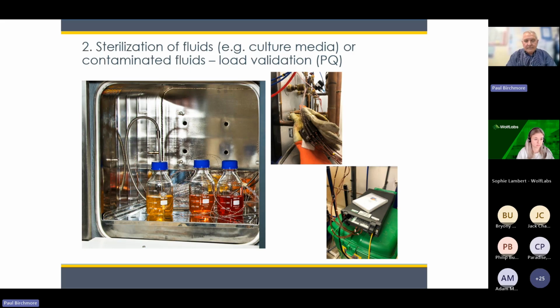That's the sort of default setting. But you can test. You can then go a step further and prove evidence of that effectiveness, performance, by filling the chamber with many thermocouples in the initial phase of the testing process, the load validation process. And you will log that. There are up to 12 thermocouples inside the chamber, fed through the sidewall through a pressure restrictive valve, and that allows you to log the data.